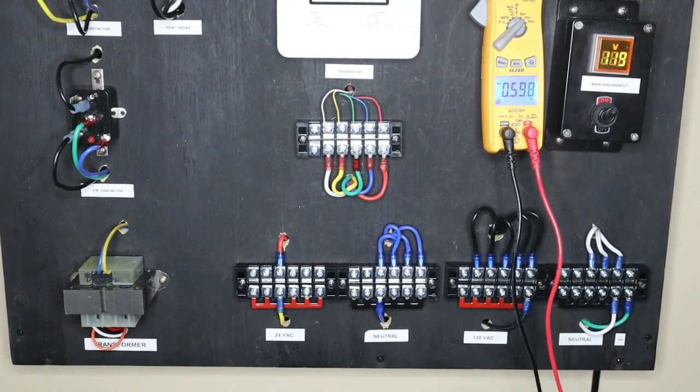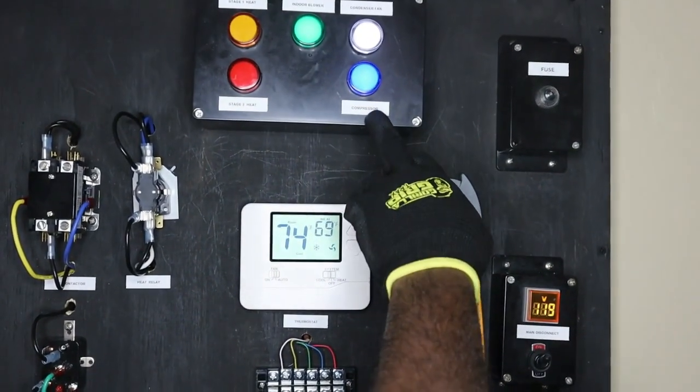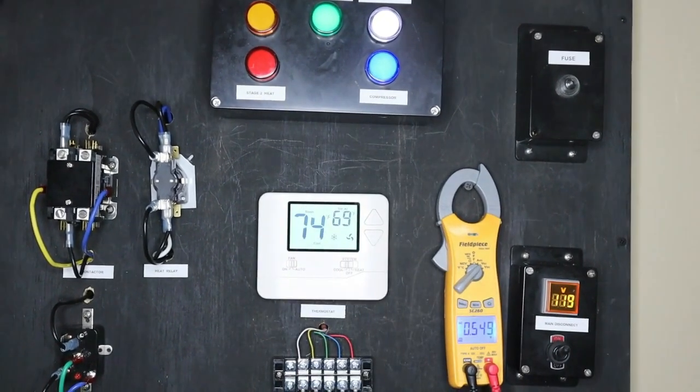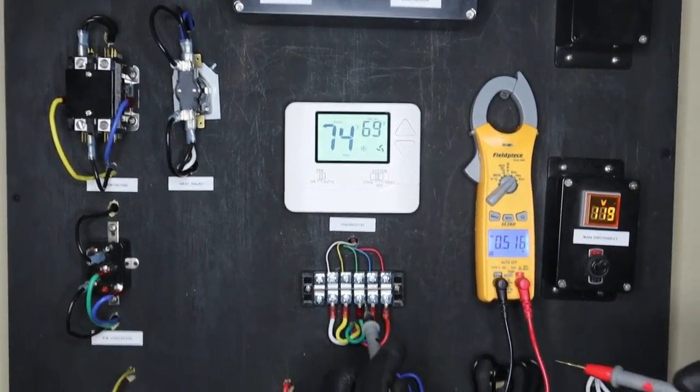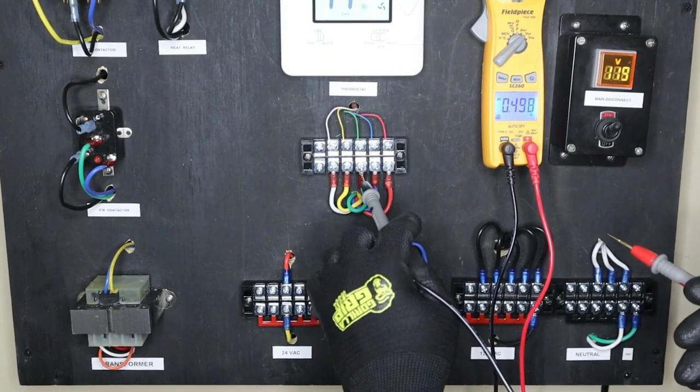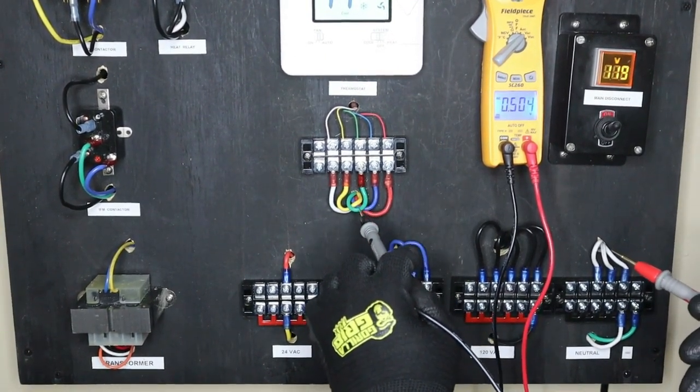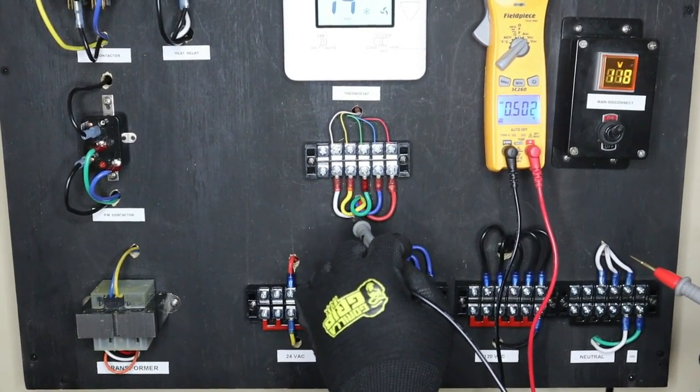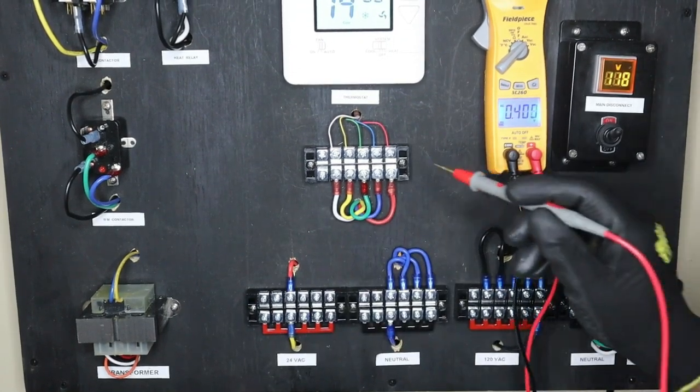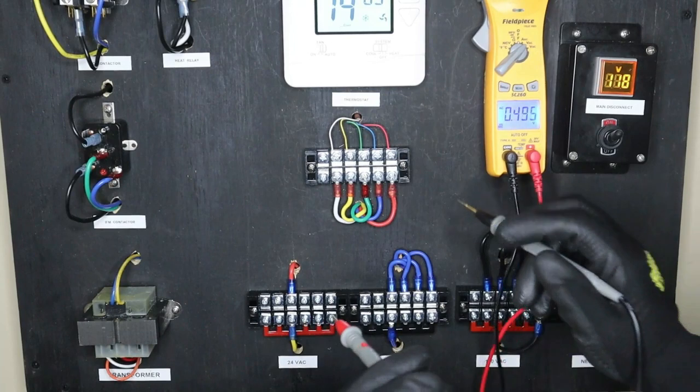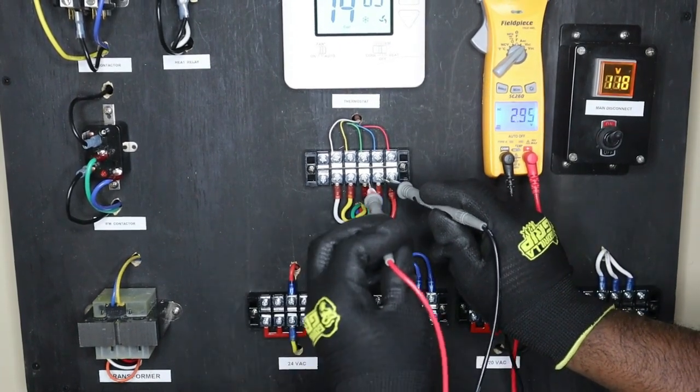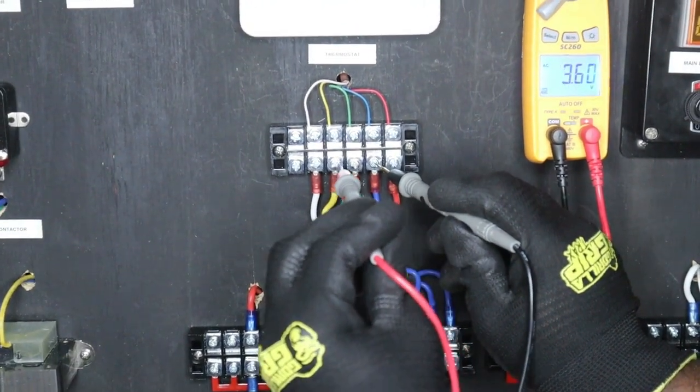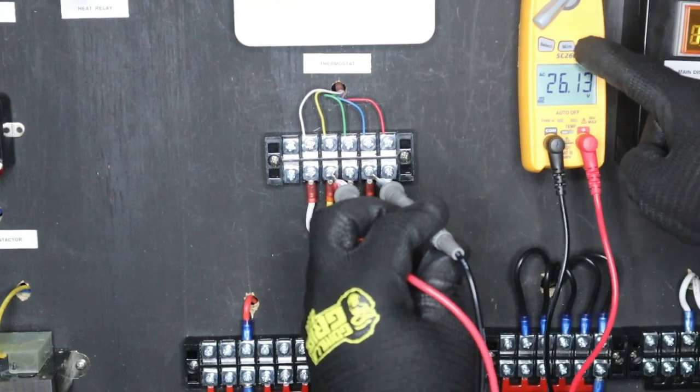Now currently as you can see the compressor is on, the condenser fan is on, and also the indoor blower is on. So with that being said I should have 24 volts on my indoor fan motor hot. I should also have 24 volts on my cooling which is my yellow wire, so I can place one multimeter lead on the neutral. I should have 24 volts here, measuring 26.